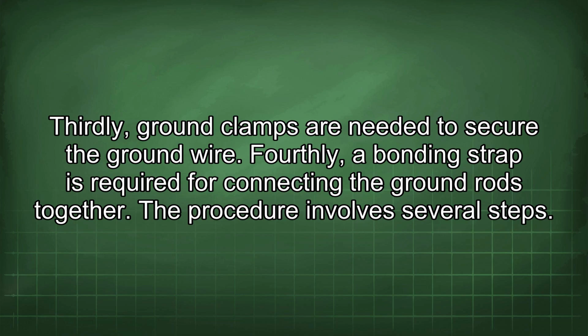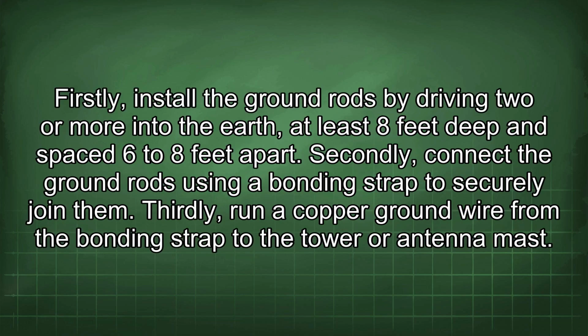The procedure involves several steps. Firstly, install the ground rods by driving 2 or more into the earth, at least 8 feet deep and spaced 6 to 8 feet apart. Secondly, connect the ground rods using a bonding strap to securely join them.